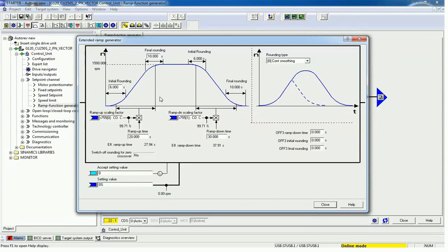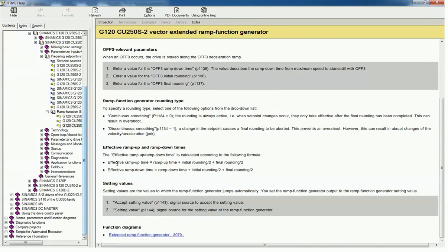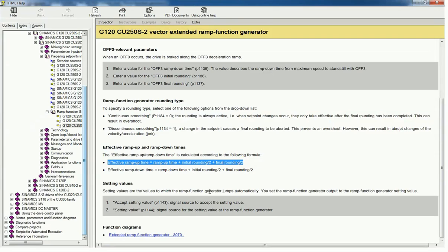From the help menu we can see: effective ramp up time = ramp up time + (initial rounding / 2) + (final rounding / 2). This equation gives us the effective ramp up time and effective ramp down time.